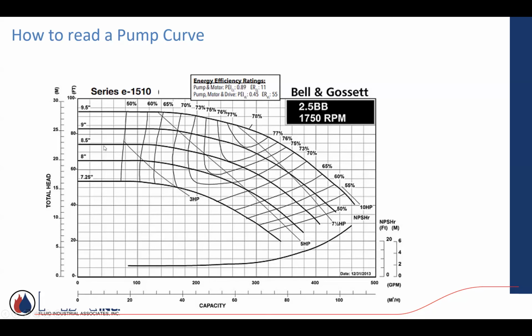The first thing that's going to highlight is that instead of calling it a pump curve, we're going to call it an impeller or performance curve. It's very specific to the impeller you select. And you're going to select that impeller, or the computer software is going to select that impeller, based on your design conditions. How many gallons a minute at what pressure drop, at what feet of head? And where this comes into play is right at the very beginning tonight, when we were looking at centrifugal pumps. We were looking at the cutaway of a pump, and we had the diameter of the impeller sitting inside the volute. Then we had this cut water. And we said, hey, that circulation discharges out.